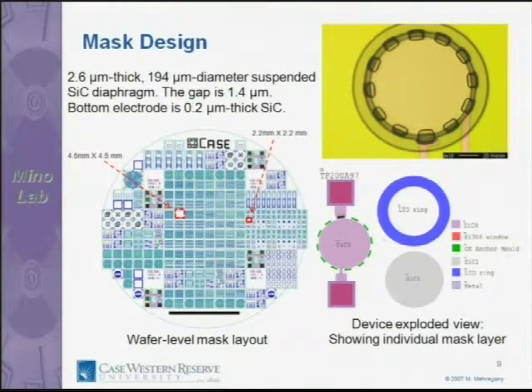I'm pointing to the diaphragm, the pressure sensing diaphragm that sits above the silicon carbide substrate or wafer by a couple of microns. When pressure is applied, this diaphragm deflects, and the gap under the diaphragm to the substrate is modulated. We essentially treat the diaphragm and the electrode underneath, sitting on the substrate, as a parallel plate capacitor. These are the two connections to the two electrodes of the capacitor, one being the diaphragm that deflects in response to pressure, so we relate the change in capacitance to the pressure applied.